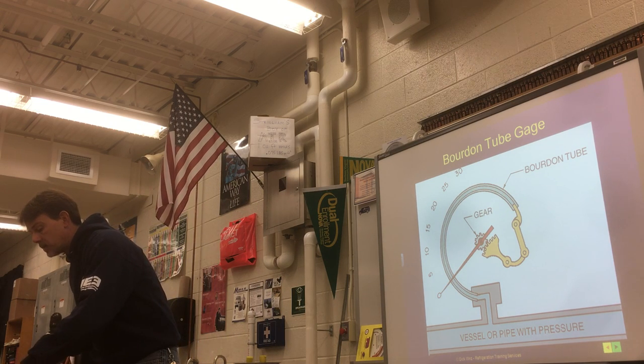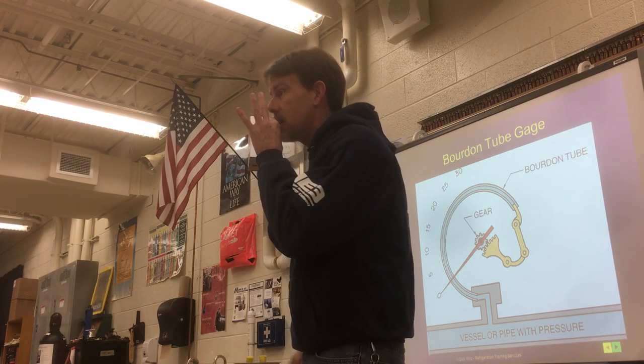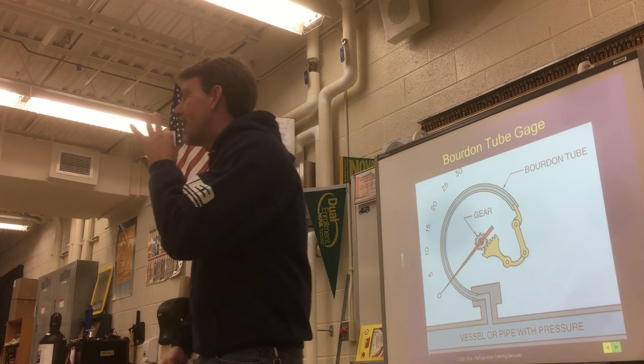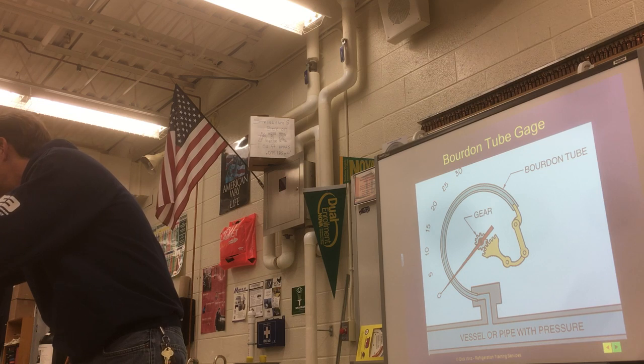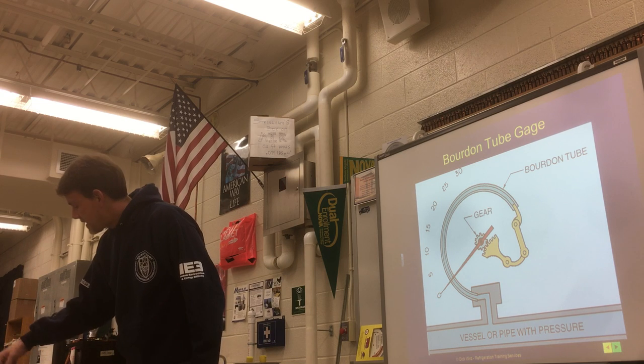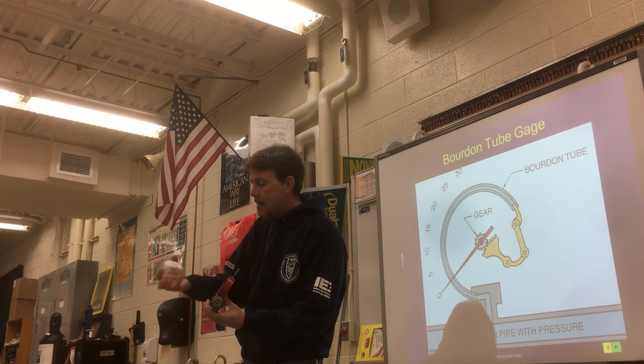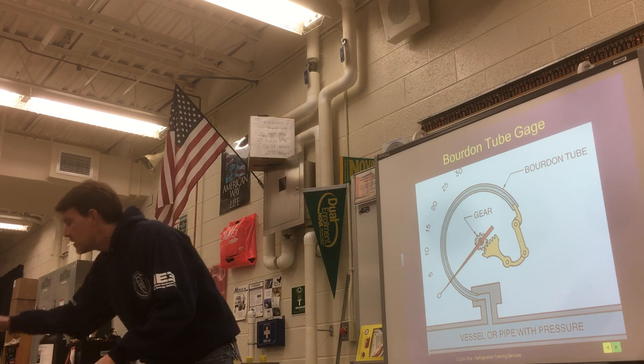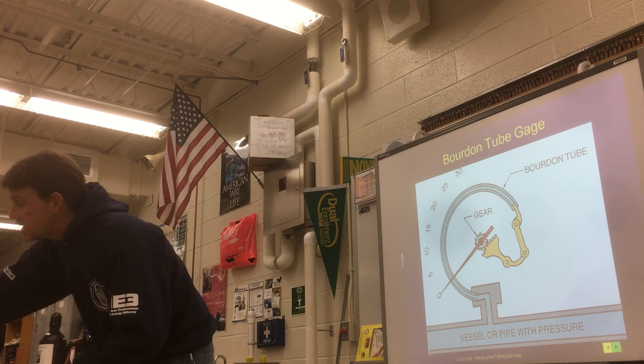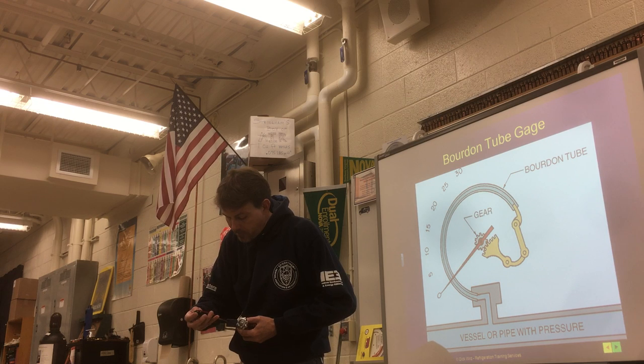For education purposes, we're going to take them apart and look at them. You had to draw something called the Bourdon tube. Have any of you ever gone to a party and got one of those party favors — all rolled up, you blow on it and it unrolls? The same thing happens with this tube. I want you to take this apart. This plastic case — some have a little cover that just pops off, others have a cover that unscrews from the front. If you've got one of the older gauges, be careful — it's glass.